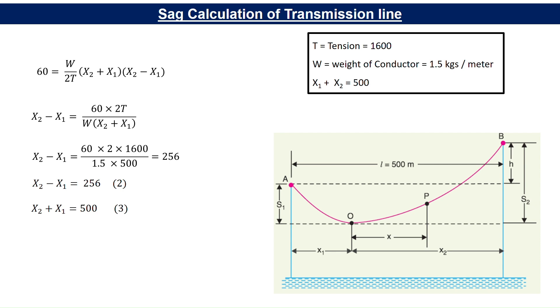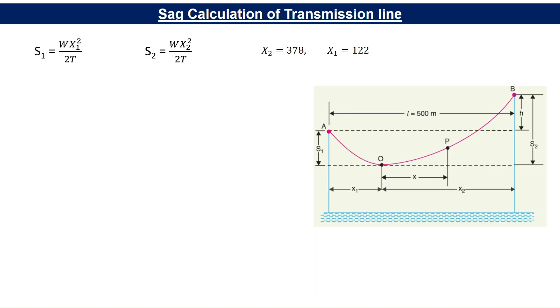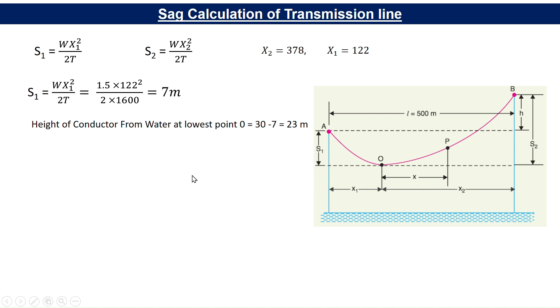Solving equations 2 and 3 simultaneously gives X2 = 378 m and X1 = 122 m. Substituting X1 = 122 into the sag formula: S1 = WX1²/2T = (1.5 × 122²) / (2 × 1600) = 7 meters. The height of the lowest point O from water level is therefore 30 − 7 = 23 meters.